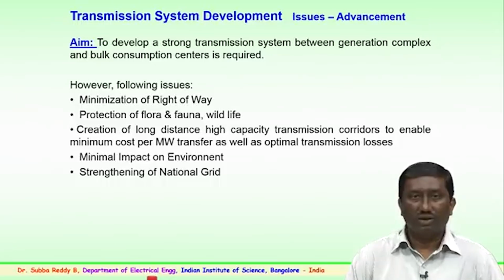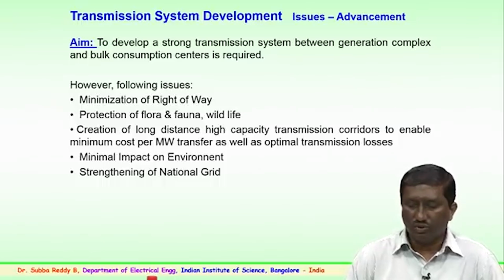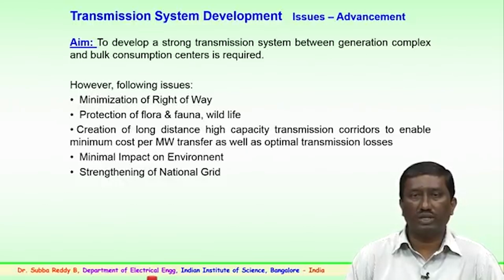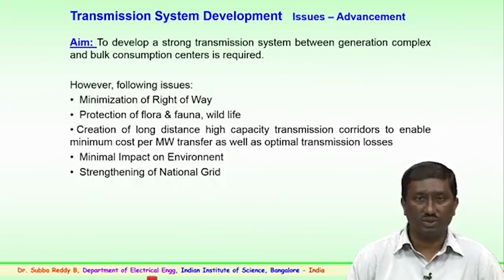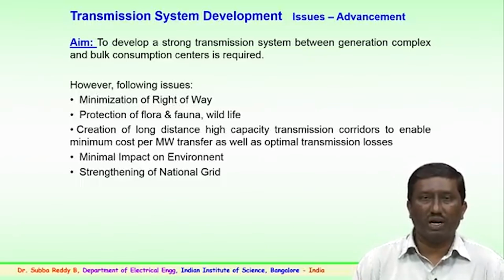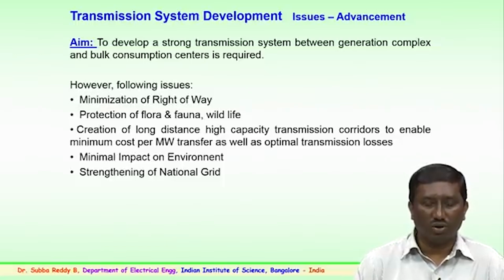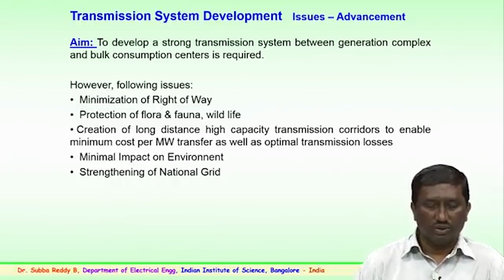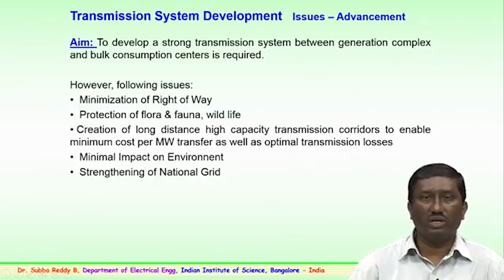Then further to this, the creation of high capacity transmission corridors will help to enable the minimum cost per megawatt transfer as well as optimal transmission losses. That is the main reason for going in for UHV transmission systems. Apart from that, as we looked into, protection of flora and fauna, and also because of the high voltage transmission system, the impact to the environment should be minimal. This is a requirement that a utility or the government has to bear in mind when they are going in for a long distance transmission. Then further, strengthening of the national grid will be very helpful to control the entire grid through a single point system. So, these are some of the issues which are to be addressed, and what the issues are and how the advancements have taken place by overcoming them, we will be looking into.